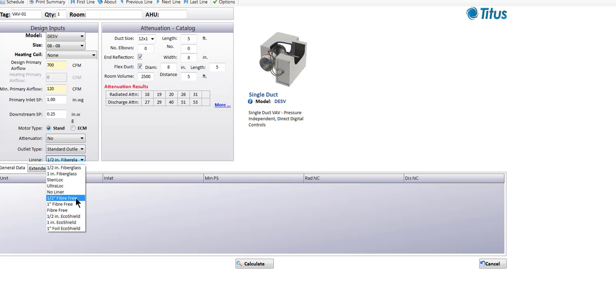We've also got options for fiber free lining, available in half inch and one inch thickness. The fiber free lining material is called engineered polymer foam and has some very interesting characteristics. First, it absorbs no moisture whatsoever. It also has an antimicrobial chemical agent throughout the material. So if you're putting boxes into a tropical environment where people have problems with moisture and mold in ductwork, you'd definitely want to go with a fiber free material.